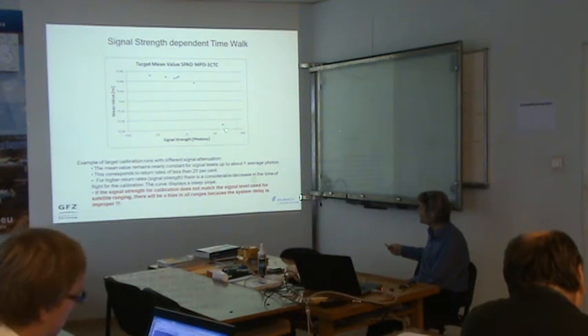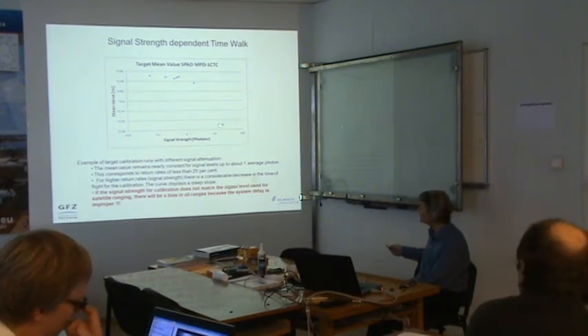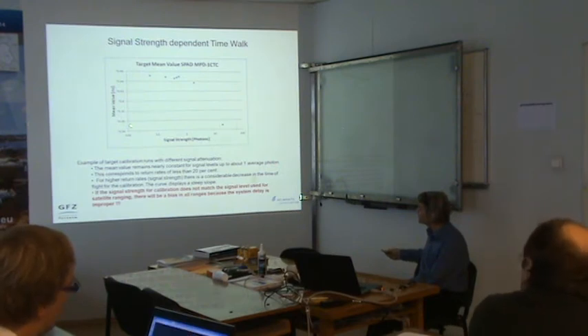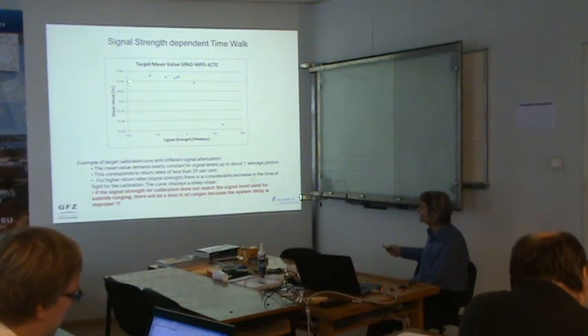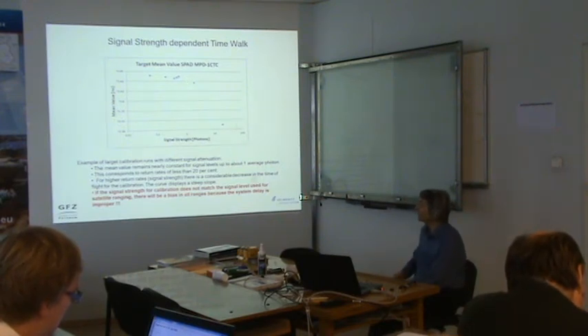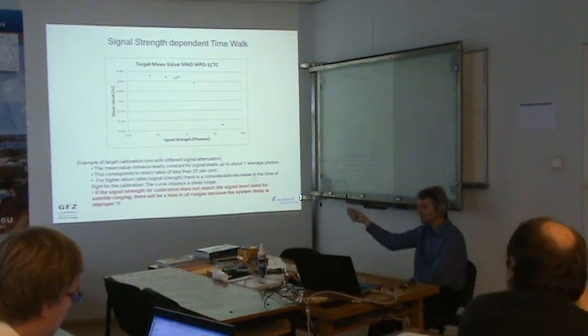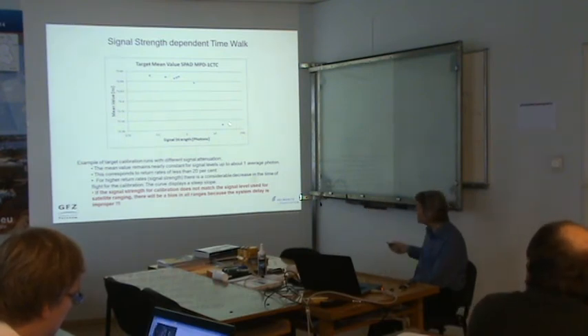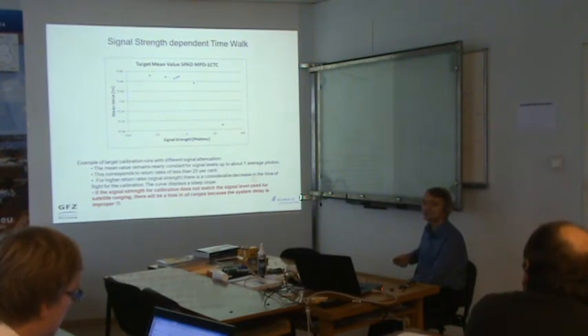And for 10 and more, 20, 30 photons average signal, the curve has a very steep slope. That means if the signal strength for calibration does not match your level, in case you apply too high a return energy to the calibration, you get a shift with respect to the average you should have at the low signal level, where you are performing your satellite measurements. And it is sometimes observed that the operator of the system says, now calibration, I'm hungry, I'm sleepy, I want to go home, let's take 50% return rates, then it's over in 1 minute. Nice, but you get an unavoidable shift in this case. Here we are on the order of 100 picoseconds. 100 picoseconds sounds not much, but it's in the order of 1.5 centimeters. And in case we are talking about millimeters, that's bad.